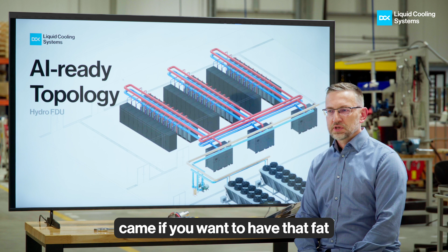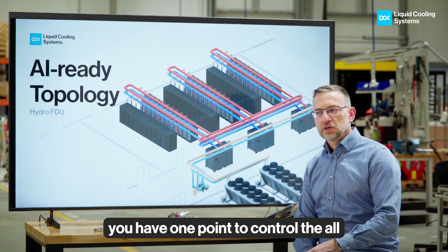So that's the topology we recommend. As you'll notice, we did one thing: we moved all those CDUs to the gray space, because if you find the right CDU, it will fit there. That's a great design, and you don't have to run a facility water system - which usually means large diameter piping, 6-inch or 8-inch, to those CDUs - so that's one set of pipes less. Secondly, you'll notice you have that extended TCS loop, which combines several CDUs and several rack groups altogether. It's all simplified, it's all better - you have one point to control all the important parameters.